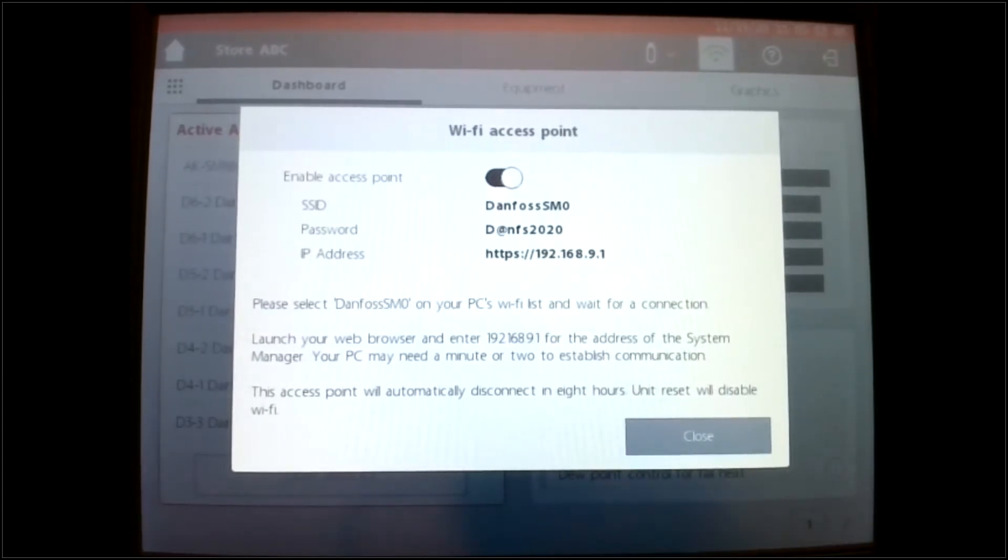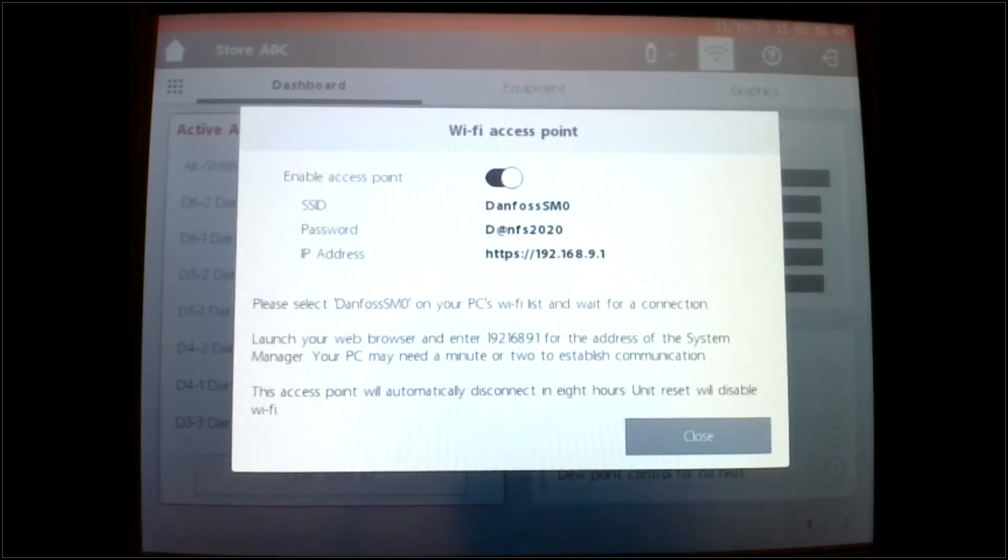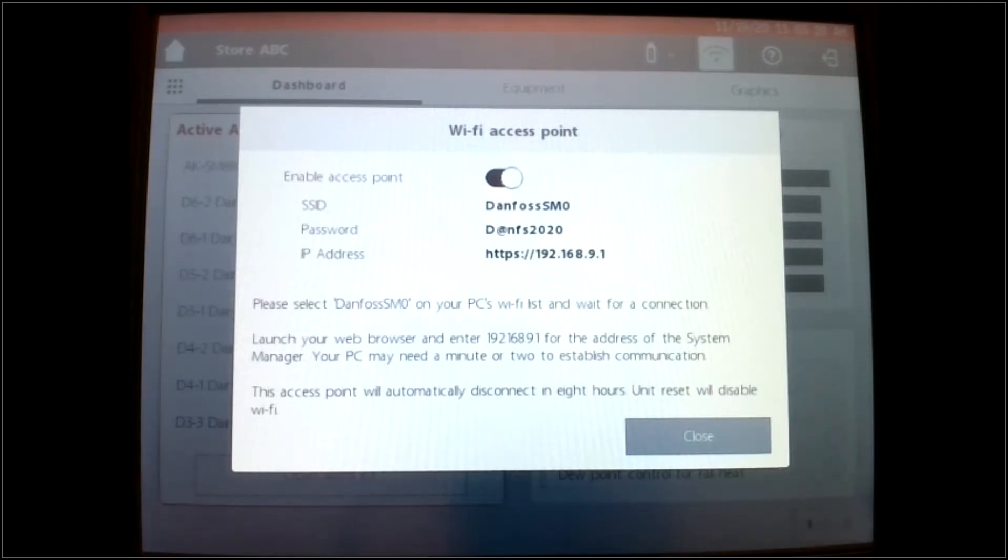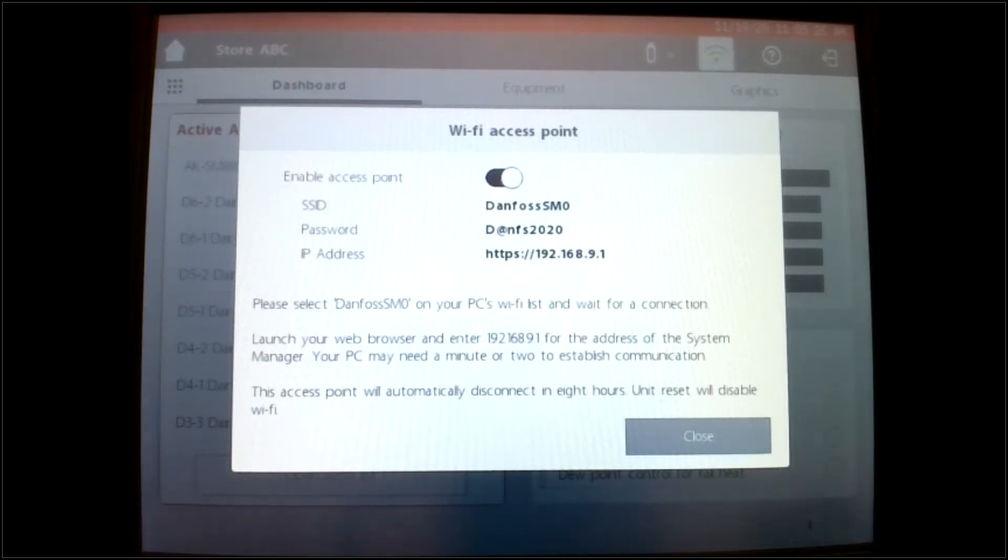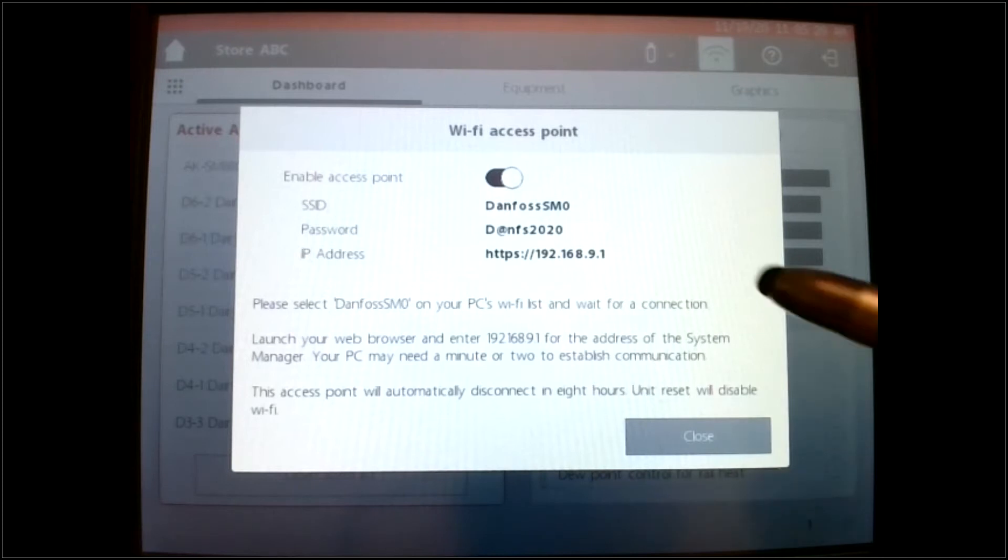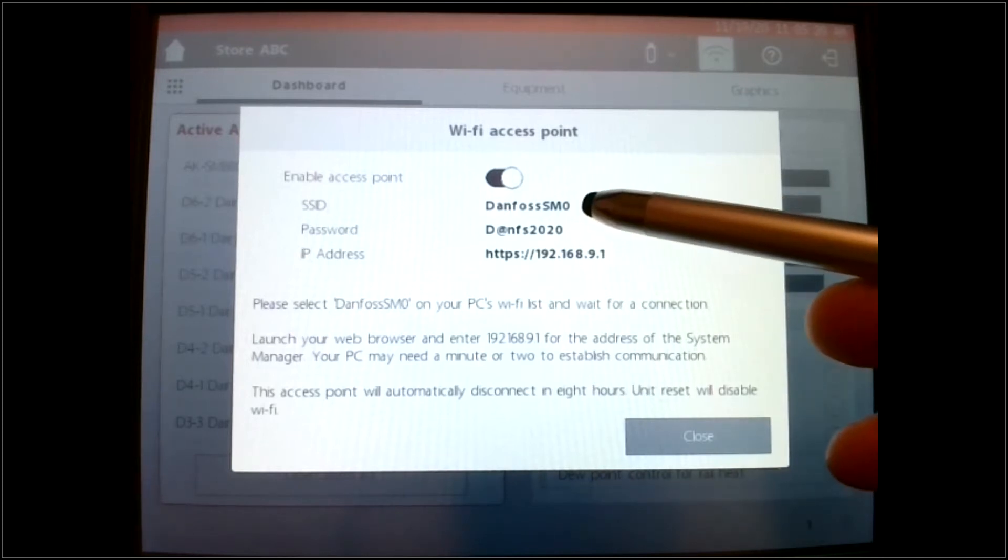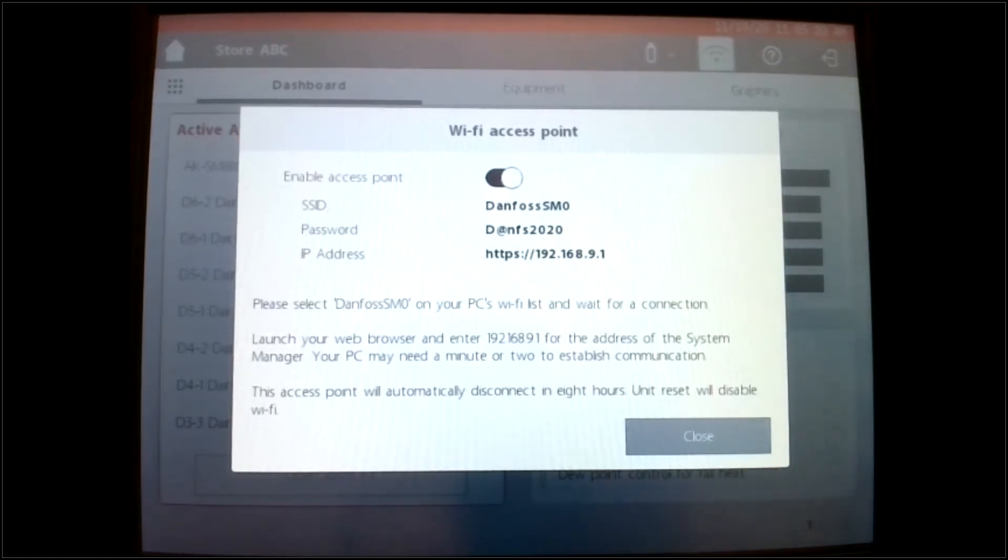and you can see that it is now giving me a network called Danfoss SM0. Now the zero is really telling me that this particular system manager is addressed as zero. If I have additional system managers at my site, they will have an address more likely as one, two, three, and so the SSID up here will be SM1, SM2. That's how you would differentiate them.